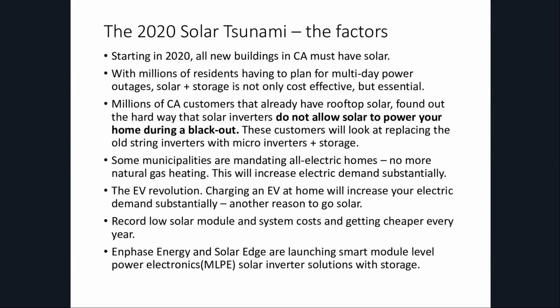I knew about this when I installed my system because I asked my electrician what happens when the power goes down. He said these inverters island themselves because you don't want your panels putting energy back to the grid when you've got a lineman working on the down power lines. It's a safety issue for the people working on them, so that's the reason they do that.